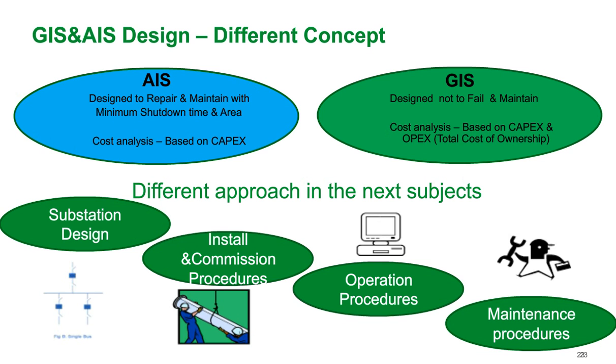Great. Another question, how about 12 kV, 15 kV, or 5 kV switchgear? Right. So now we'll just call this the 15 kV class of switchgear. The main difference between air-insulated and gas is that air-insulated switchgear, we'll focus on metal-clad for simplicity, can typically have a two-high construction. When you compare two-high construction versus GIS, which is single-high construction, single-high is 1 breaker per section, two-high is 2 breakers per section.